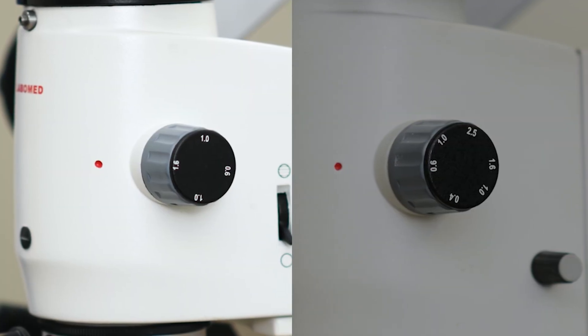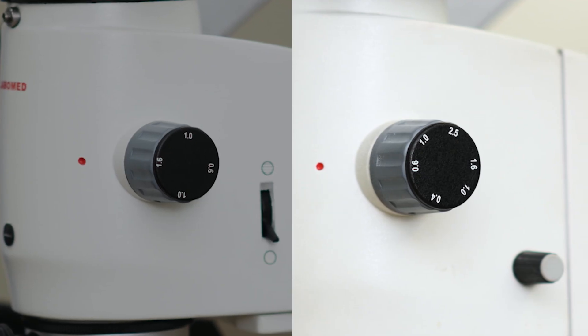That's why range of magnification is the first factor I look for when buying a microscope — both how wide the range is and what the lowest magnification is. Typically, when you pay more, you get a much wider range. A three-step microscope is cheaper than a six-step, but you will not be able to work continuously with a three-step. Our goal is to work ergonomically and continuously with a surgical microscope, and for that you need a wide range of magnification.